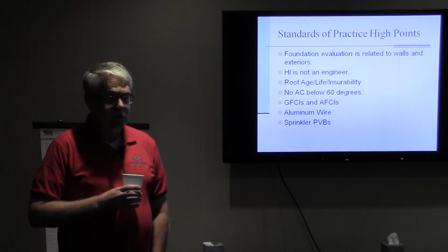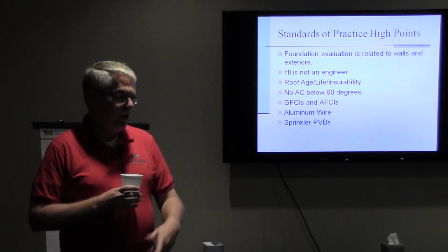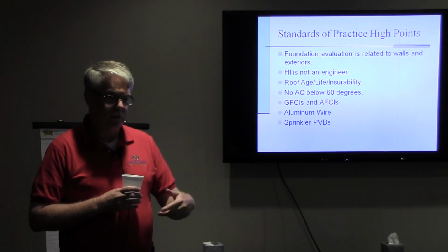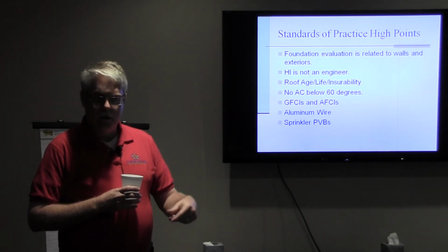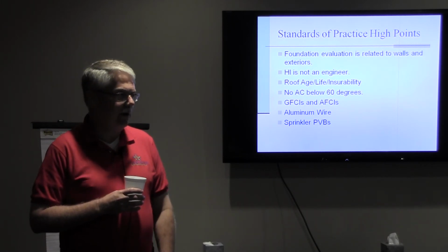But I have personally met handymen who have retrofit a house, and then they plug in an elliptical glider, a particularly high-end vacuum cleaner or treadmill. It's always kicking the circuit out. And mama calls them and says, come take your damn arc fault and go away.